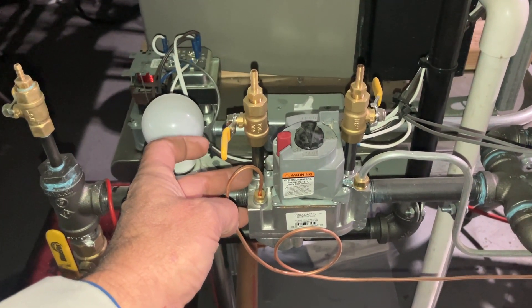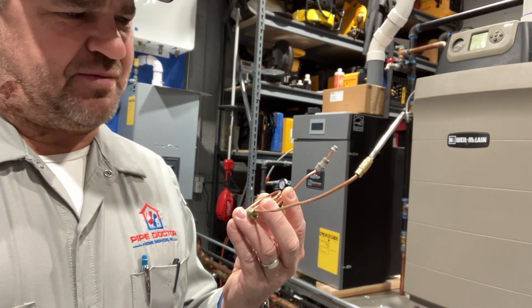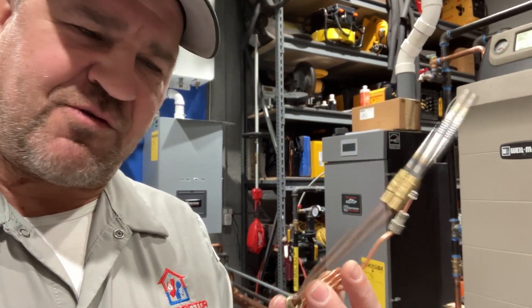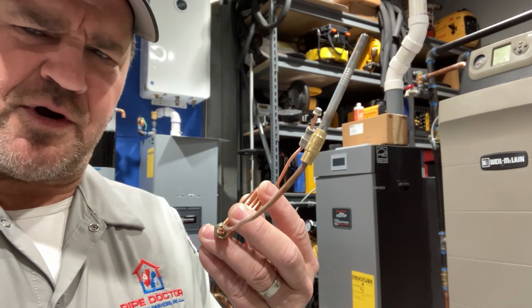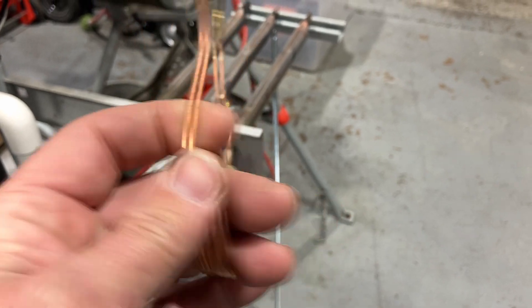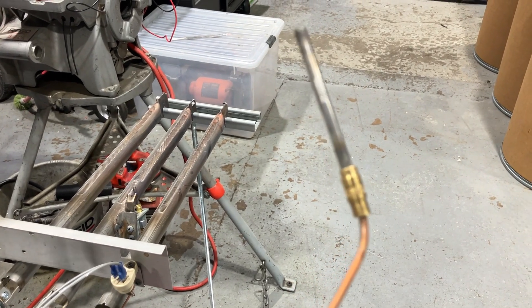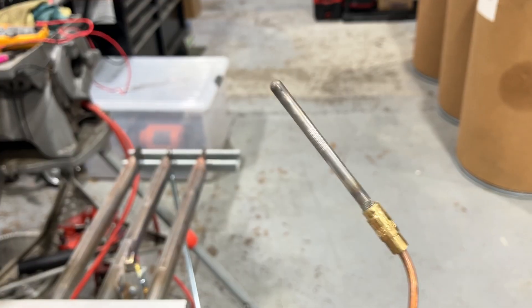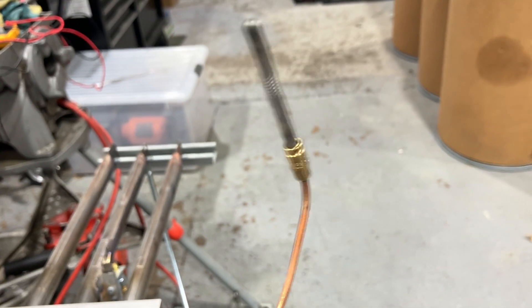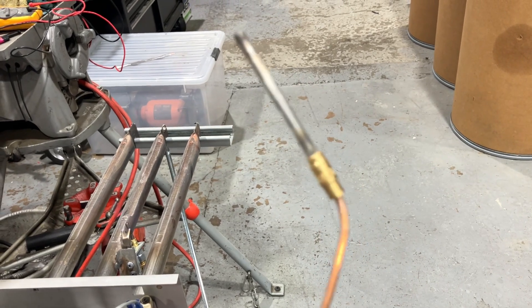So you may be asking yourself: how does this create electricity by being heated in a flame? Well, in order to answer that question you have to understand what this is and how it works. A thermocouple is made up of two dissimilar metal wires that are joined together at one end to form a junction, which is exposed to the temperature. That gives you what engineers call the Seebeck effect. When the hot junction is heated or cooled, those electrons in the two metals move differently and they create a voltage difference.